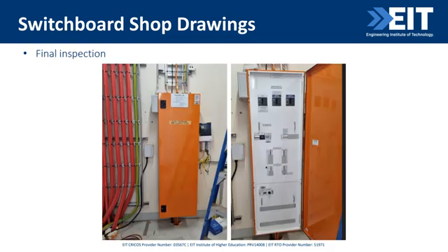So now imagine you've done your design, you've reviewed your shop drawing, and the board has been built, arrived, and been installed. So this is a distribution board. It's obviously wall mounted. Cables come in from the bottom and go out from the top. We've got our main label, and we've got some door handles here. Inside, we have some chassis, we have some breakers and isolators, and some control section down the bottom.